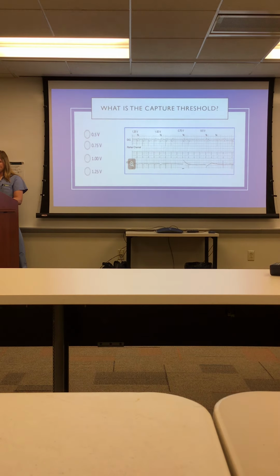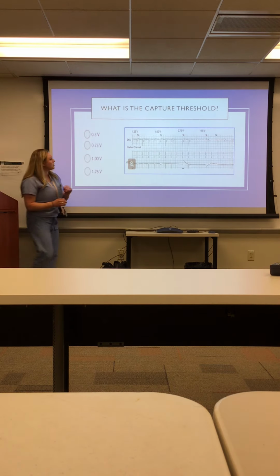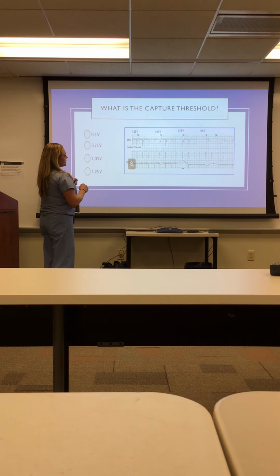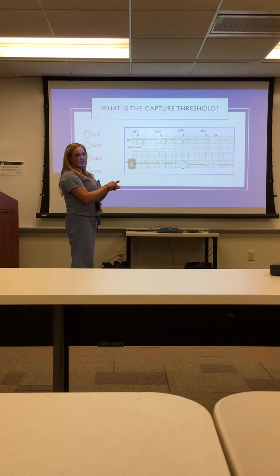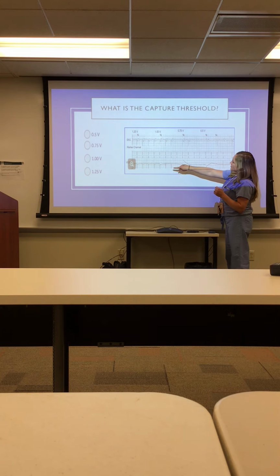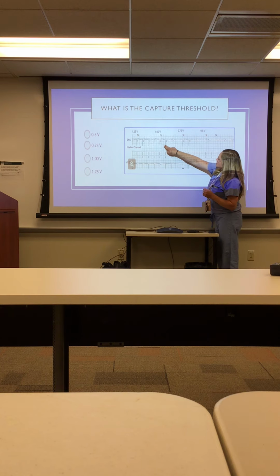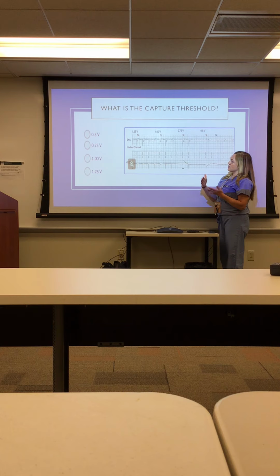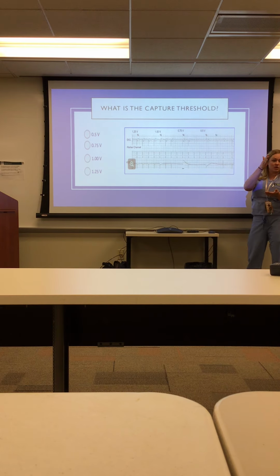Okay, so looking at this strip, we're going to determine where we're losing capture. And these volts are what we see on permanent pacemakers, but either way, on the dial, you'll see it walk down the same way in volts. So here, we're at 1.25, we see some nice captured ventricular beats. You see a pace, QRS, so you're overdriving that rate. Another way to check is whatever rate you've got it at, make sure that's what your monitor says. And we talked even earlier about, if you're not sure about it, have a second pair of eyes: if you're looking at the dial and watching to see if it's paced, somebody else can be making sure to see if you lose capture or not.